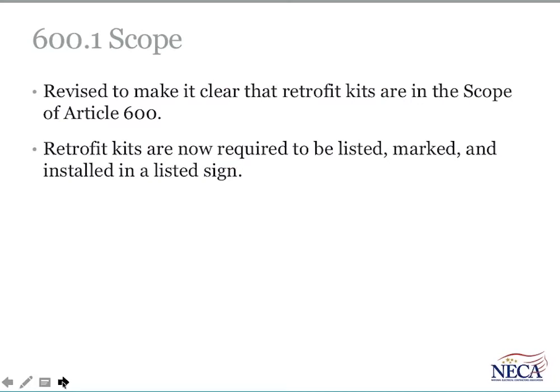And when you have a listed sign that's being changed, say for example from fluorescent technology to LED technology, oftentimes there's retrofit kits that can be used for that purpose. Retrofit kits are required to be listed and marked, and it's all about compatibility. We want to make sure that the retrofit kit being installed in a sign to bring it up to current technology is listed and suitable and has been evaluated for that purpose.